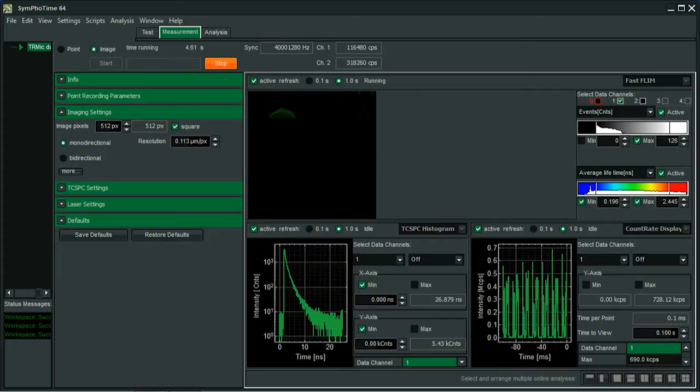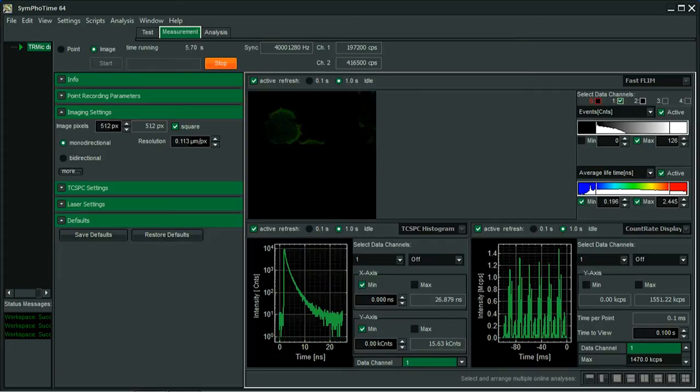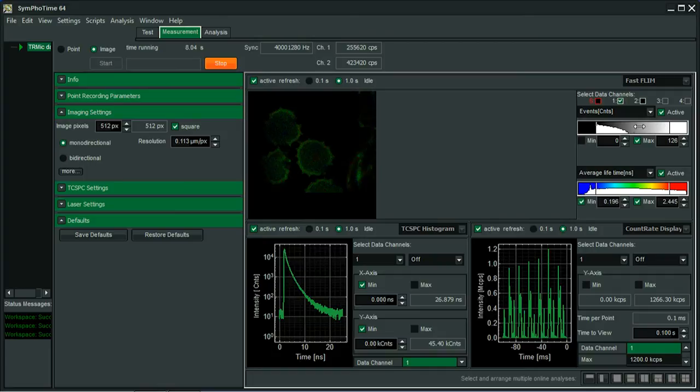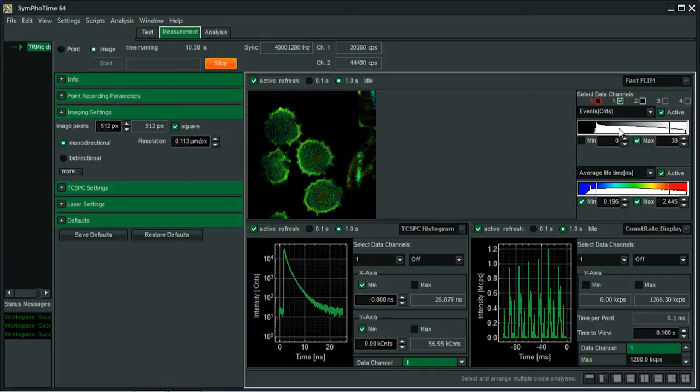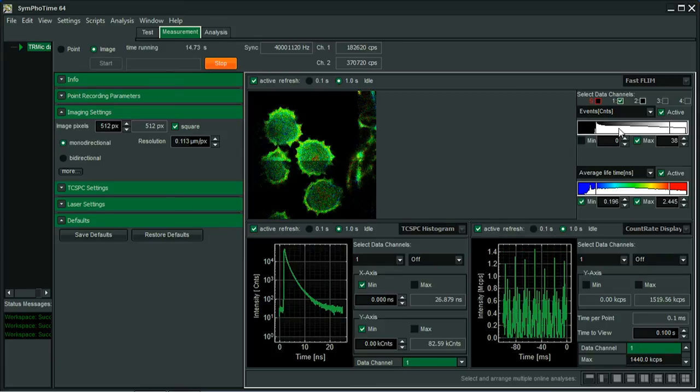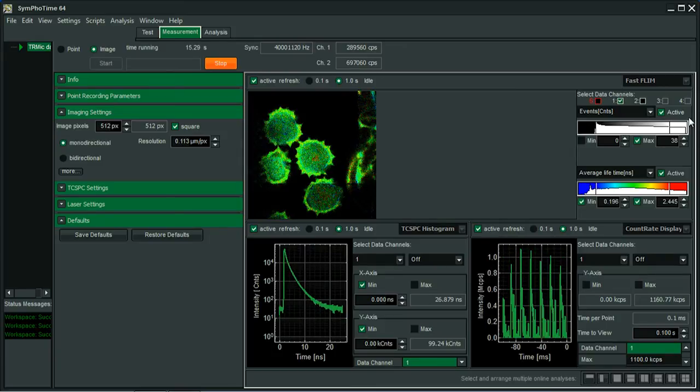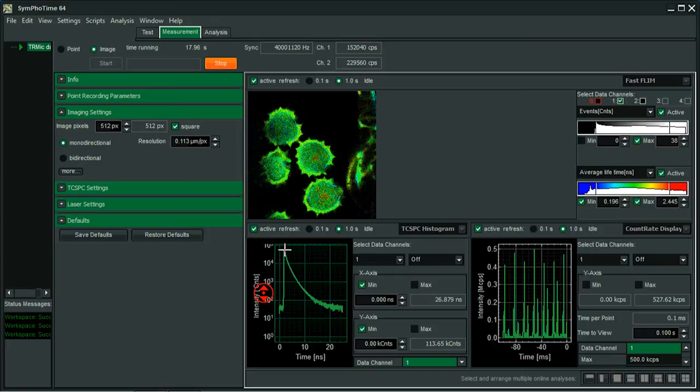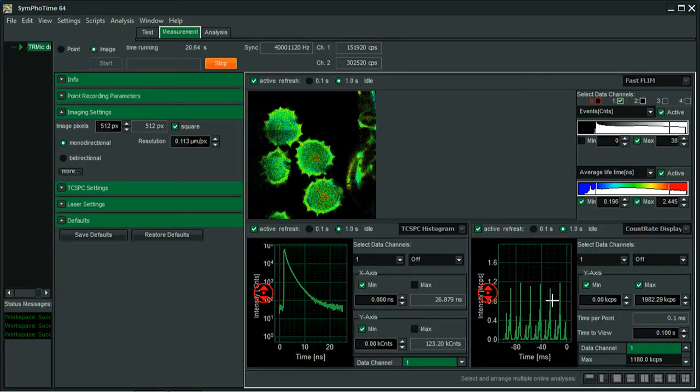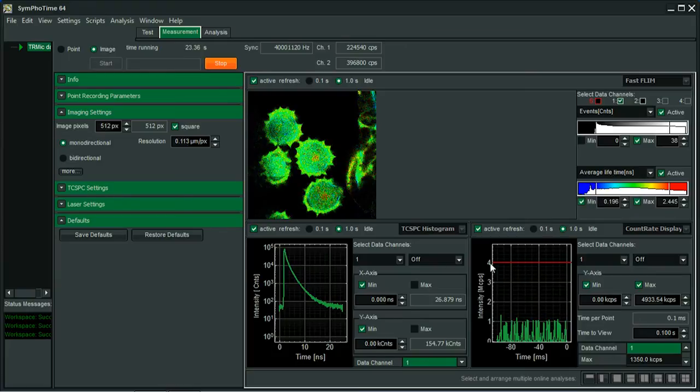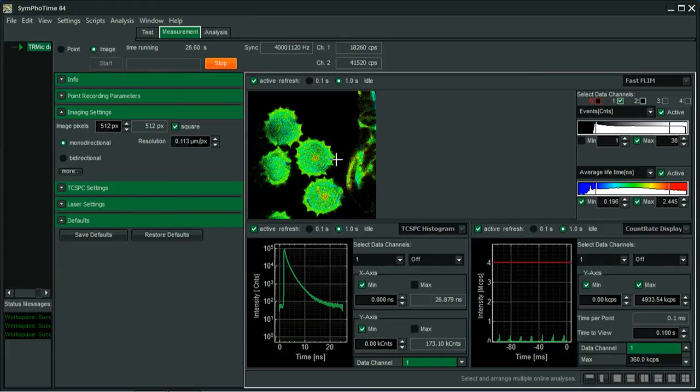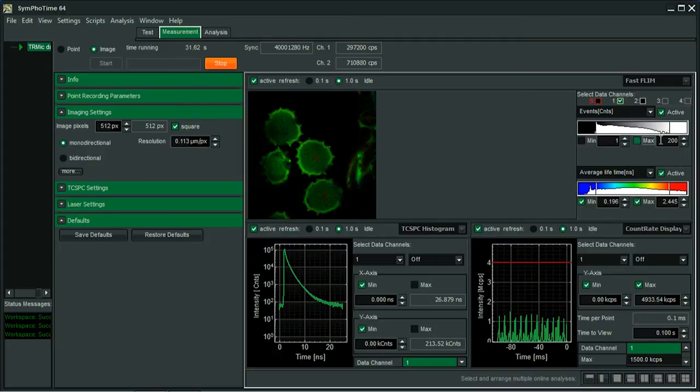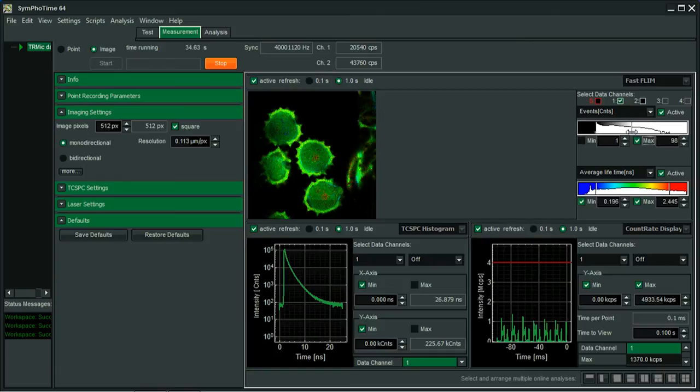Here in the record display, and due to the size of the video, we just picked one detector. What we are acquiring, we're seeing the decay in this detector, we're seeing the time trace here with this 10%, and here we can have a preview of our online image. As we acquire, we can play with the intensity and also with the FLIM contrast already.